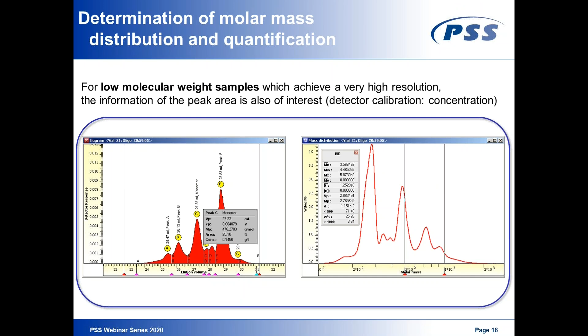And important to know for the detector calibration is that it's totally different from the calibration we've been talking about previously. For the detector calibration, you take your monomer and you inject several concentrations of your monomer, and then you get a response factor for the detector for your monomer. And using this response factor, you can calculate the concentration from the area. So like you would do it in HPLC. So for low molecular weight samples, it's very often possible to get both the molar mass distribution plus an additional quantification in the low molar mass area.